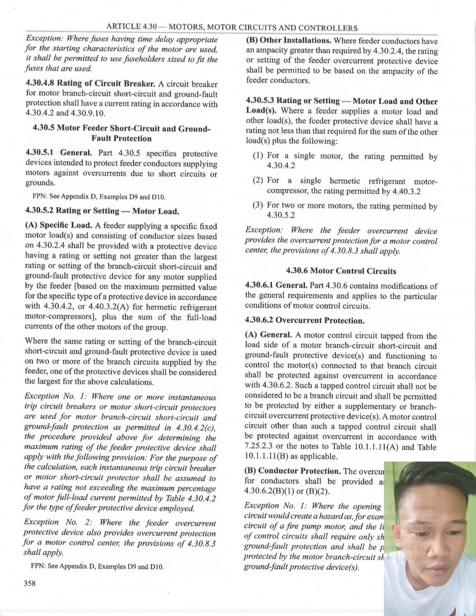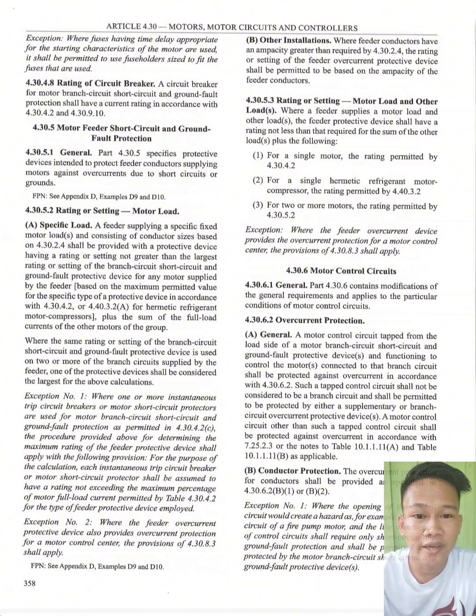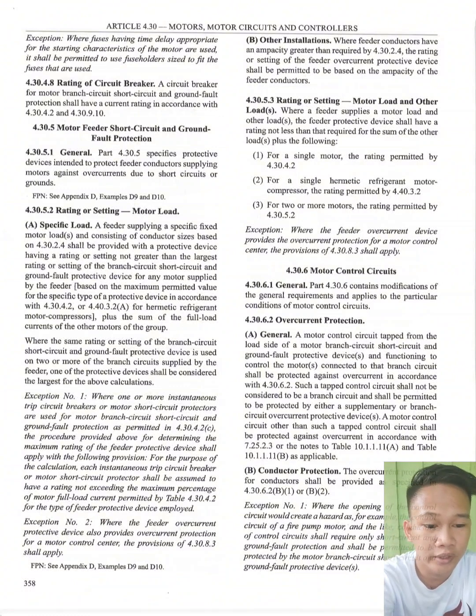Second, for a single hermetic refrigerant motor compressor, the rating permitted by 4.40.3.2. Third, for two or more motors, the rating permitted by 4.30.5.2. We have the exception: where the feeder overcurrent device provides the overcurrent protection for a motor control center, the provision of 4.30.8.3 shall apply. So we will look at 4.30.8.3 later.